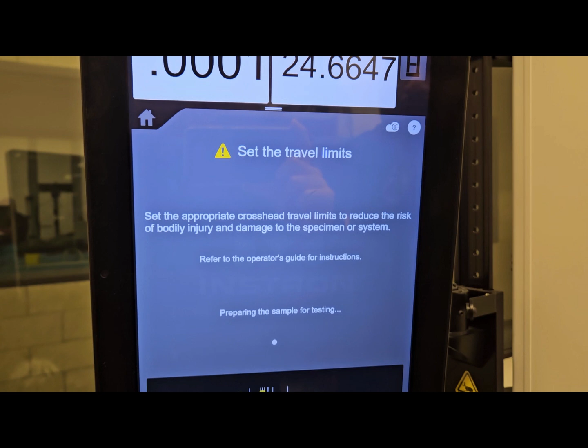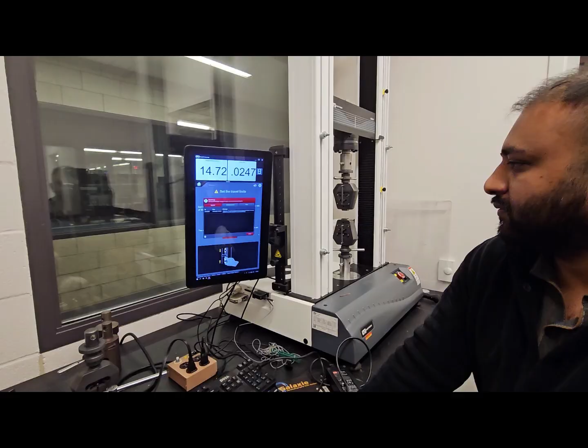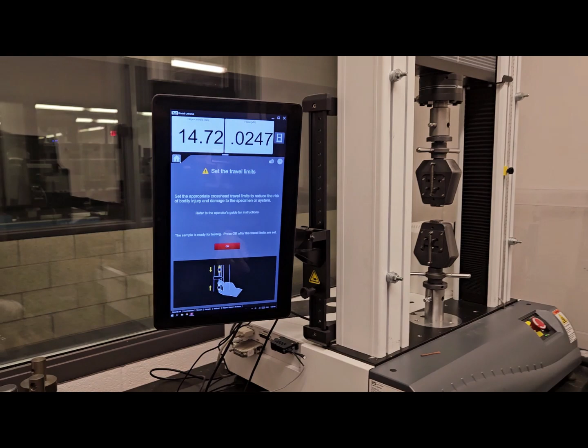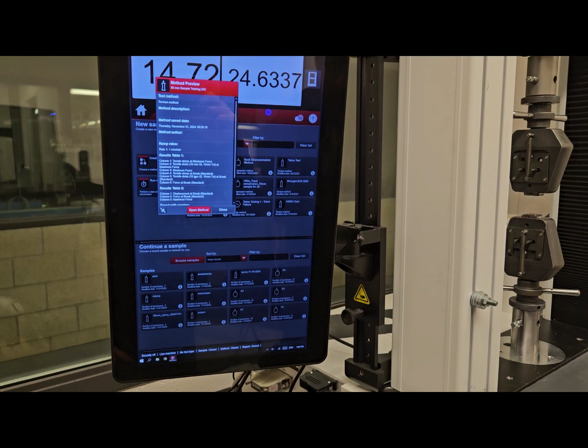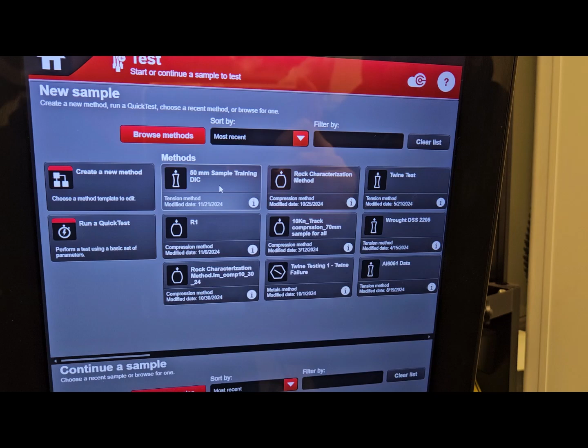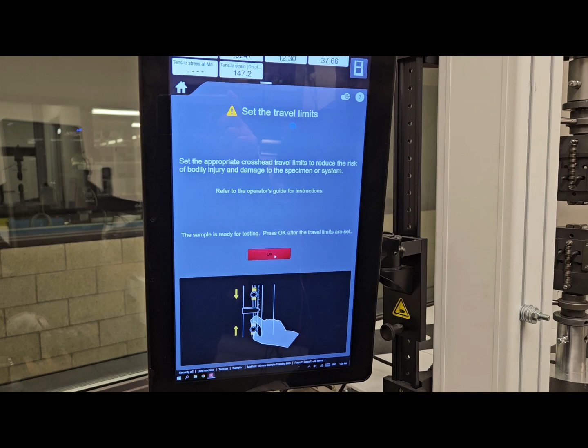And now you can see here, this test we can do, it will move up and down. It will not move unless we open that software, and make sure this should be above this line. Now since we are using this 50 mm duplex stainless steel sample, we need to use this method, 80 mm sample DIC or this DSS 2205. Double click over here, press OK.